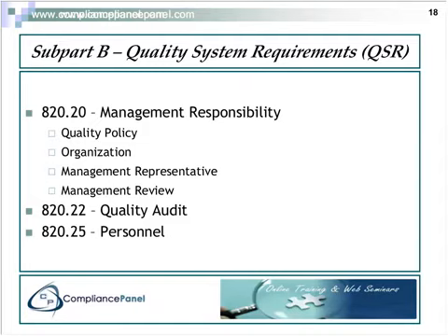When the FDA refers to management, again, they're referring to the individual with the highest authority in the facility. It is ultimately their responsibility to ensure that these QSR requirements are properly implemented. And management is also responsible for establishing a quality policy, providing an organizational structure with necessary resources with the proper interrelationships between the disciplines, and for appointing a management representative, as I said earlier.